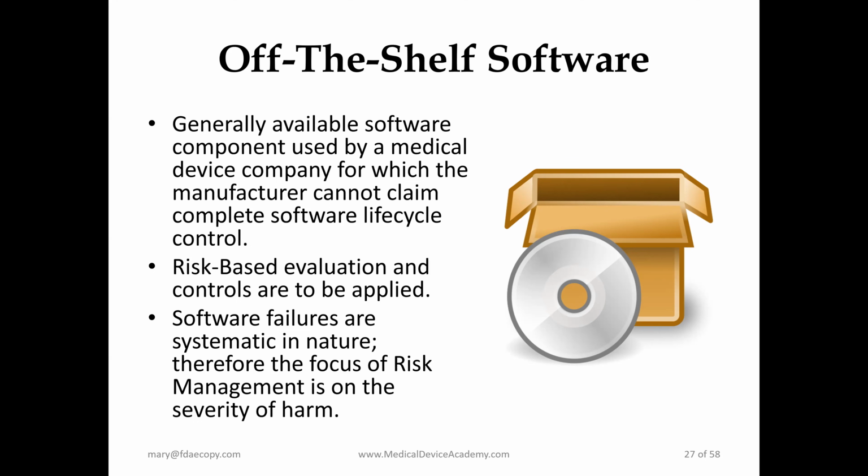The important part of understanding what you need to do if you have off-the-shelf software is understanding that it's a risk-based evaluation. It depends on the potential harm of the device to the user and the patient, and that determines what degree of control you need to have on your off-the-shelf software.